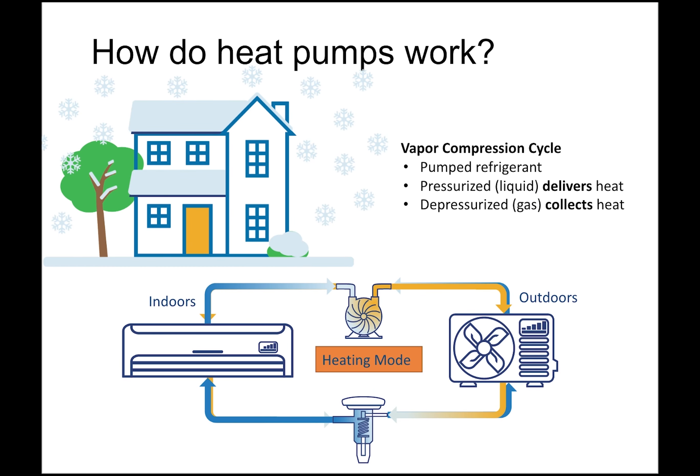Cold climate air source heat pumps work through the use of the vapor compression cycle, combined with advanced refrigerants, variable speed drives on the compressor and fans, and an algorithm-driven control system. Although heat pumps of the past also utilized the vapor compression cycle, they do not include these additional features that provide greater efficiency and cold weather operation without supplemental heat. The cold climate air source heat pump is able to toggle between heating and cooling mode simply by the flip of a switch.